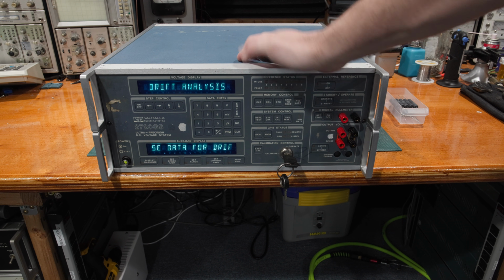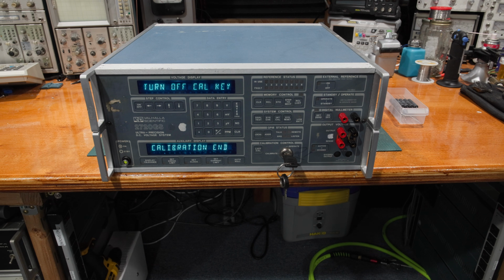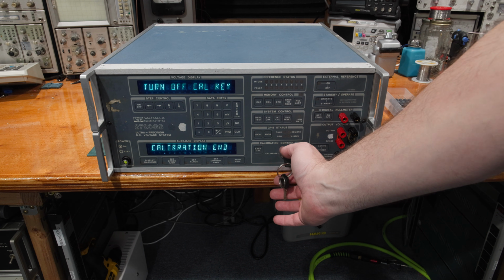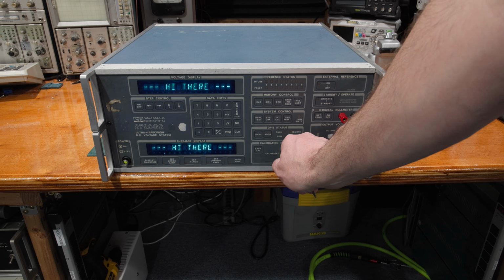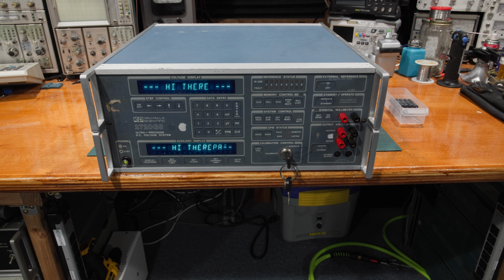So we'll leave this on. We do not want drift analysis because the unit got repaired and all the voltages kind of went out to orbit. So drift analysis is useless data at the moment. We're going to go turn off the cal key. And now we'll do an internal calibration. We'll do an internal cal here in a little bit.